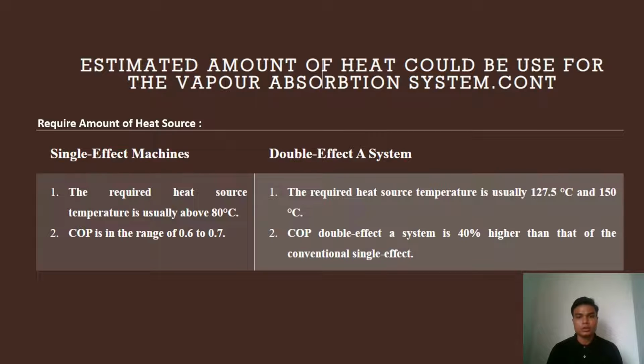And the required heat source temperature is usually 127.5 Celsius to 150 Celsius for a double effect machine. And the COP in a double effect system is 40% higher than a conventional single effect.